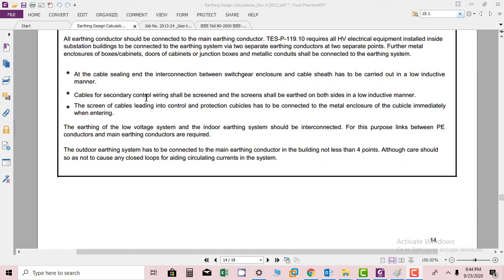Cables for secondary control wiring shall be screened and screens shall be earthed on both sides in low inductive manner. The secondary wiring should be grounded. It is also recommended as per specification from both sides.